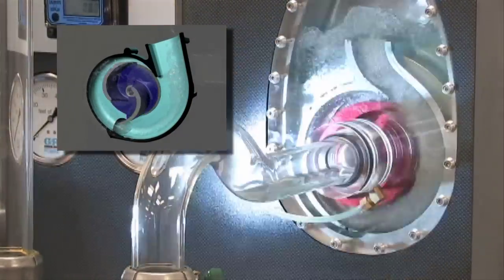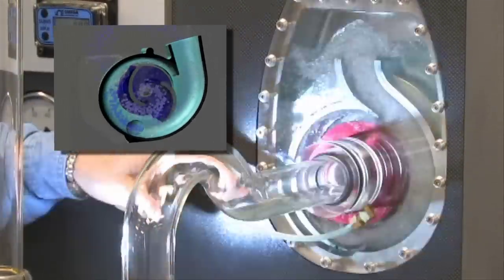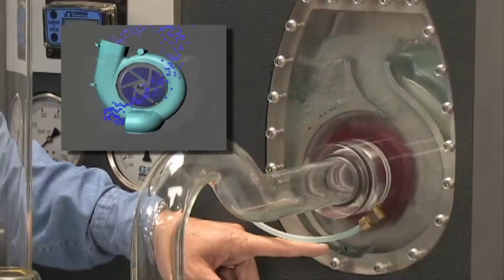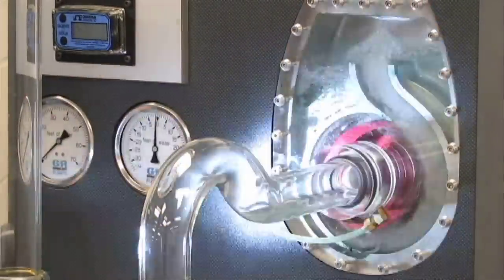Inside this discharge chamber, the air and water separate. The heavy water falls back down through a recirculation port and the air then is evacuated through an open-ended line or through an air release device.